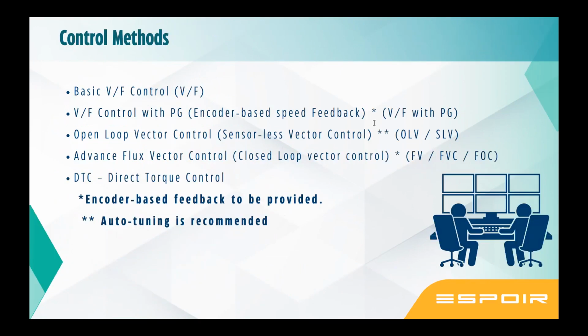So this is all about the selection and engineering we discussed. Now we go to the control method. Now a VFD, as I said, changes the frequency. How do we change it? By converting to DC, then again putting it back into AC. So now there are control methods available. As I said, V by F: we are changing the voltage as well as the frequency. Now, in changing voltage and frequency, there is a pattern. You cannot just change it however you want. There is a pattern that is given.